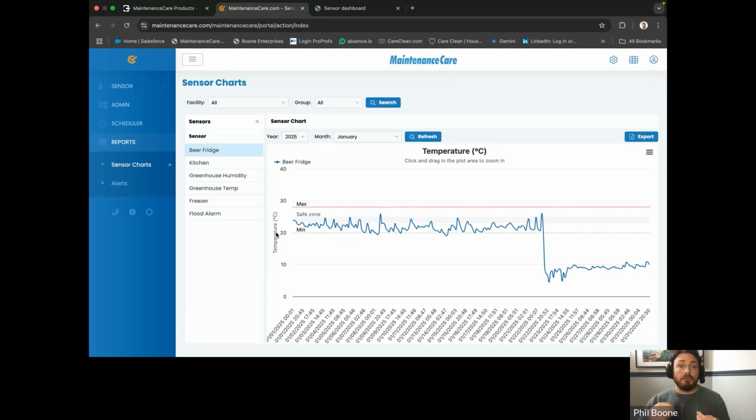But what we do for long term, keeping your temperature readings, instead of having them, the sensors themselves actually give off readings every 15 minutes by default. So instead of keeping every single reading that's ever happened, we actually isolate when it's running optimally. So in this sense, I have it running, it keeps the record at midnight, it keeps it at 11 a.m., at 6 p.m., at midnight again. So you get 4 throughout the day, which gives the municipality the correct readings, showing that you aren't maybe neglecting an ambient room temperature, or all of the food in your fridge has gone bad, right? And that's the most important part.